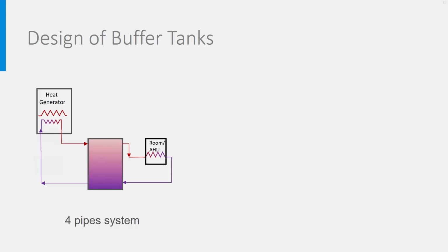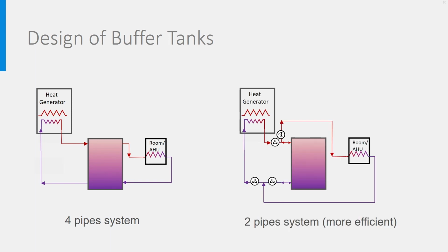Finally, a last word about the design of buffer tanks. A disadvantage of these 4 pipe systems that you see on the left and that we used all along this presentation is that all water has to flow through the tank, causing high flow rates in the tank and more mixing and less stratification. The 2-pipe system is therefore often preferred, where the hot water from the generator can be directly led to the room and air handling unit when needed. If there is no heat demand, then the hot water from the generator is stored in the tank. And as a third option, the generator is not working, but the needed heat is taken from the tank. This needs, of course, an accurate control strategy of the charge and discharge of the tank.